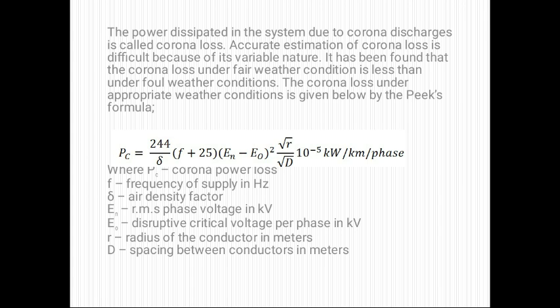Pc is equal to 244 upon delta into (f plus 25) into square root of (r upon d) into (E minus E0) square into 10 to the power minus 5 kilowatt per phase per kilometer. Now here f is the frequency of supply, delta is the density factor, E is the RMS phase voltage, E0 is the disruptive critical voltage, r is the radius of the conductor, and d is the spacing between the conductors in meter.